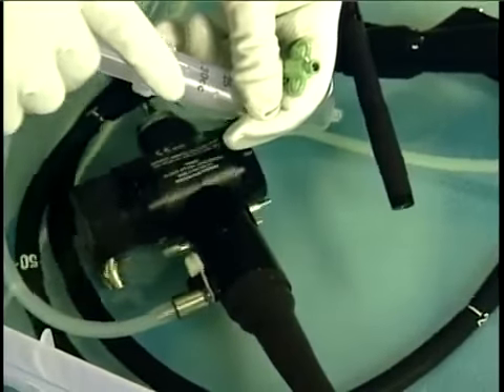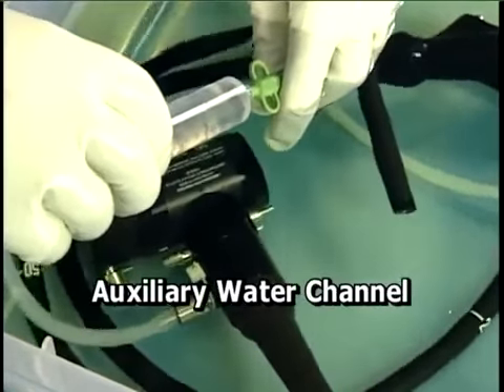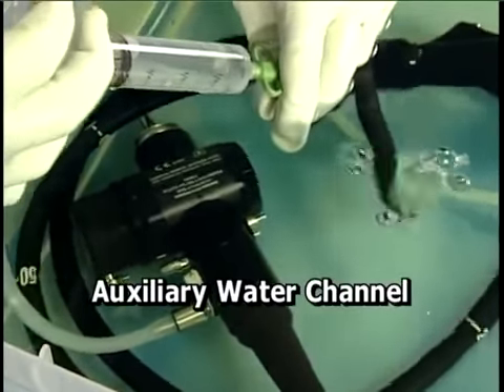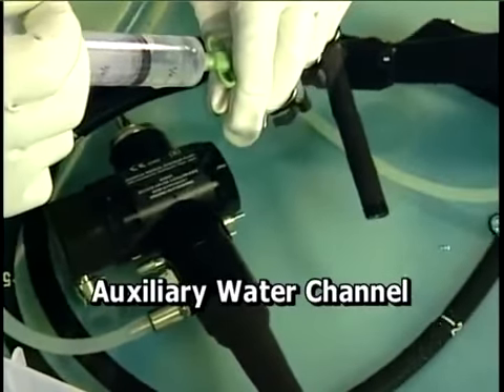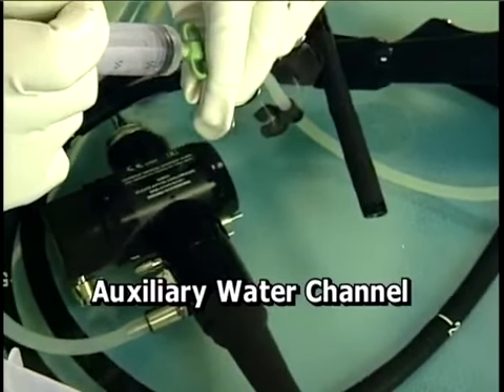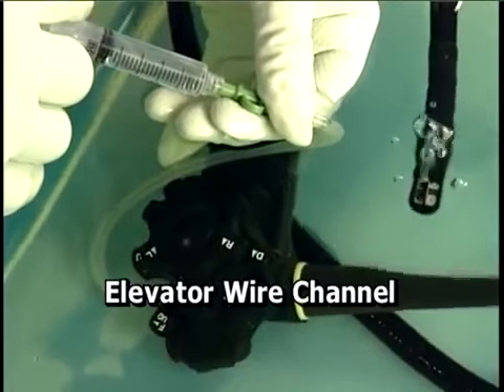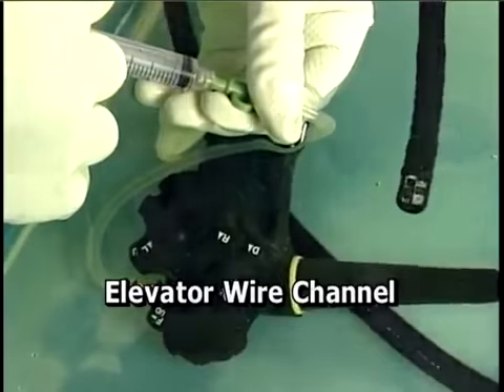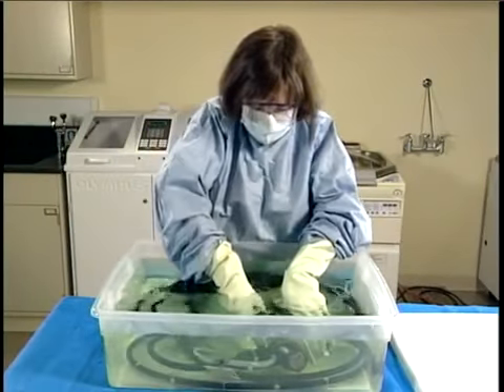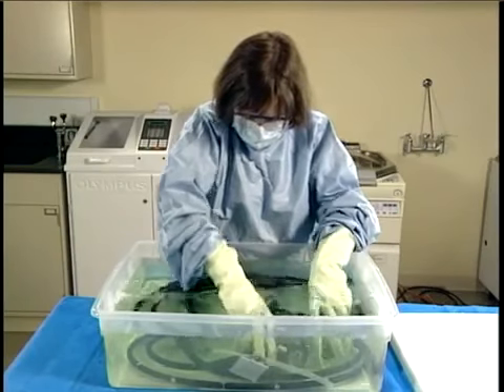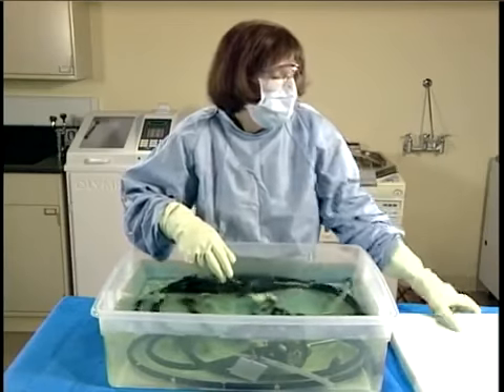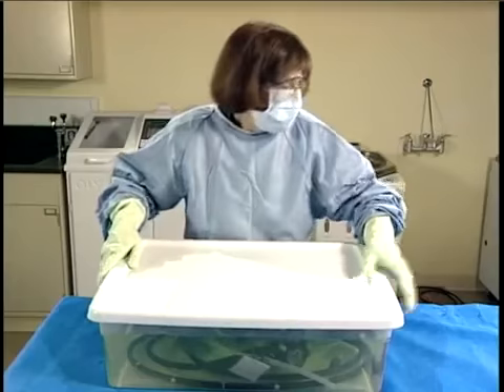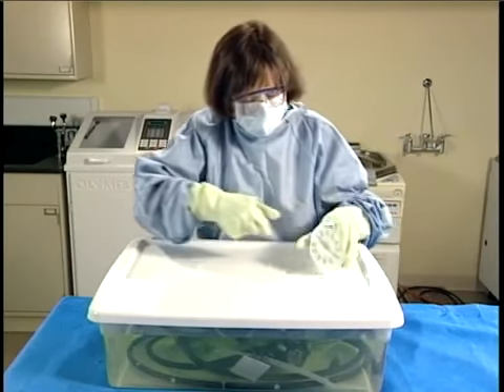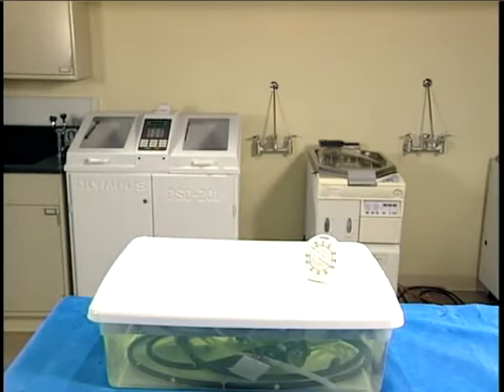If you are reprocessing an endoscope with a special channel, use a syringe to inject disinfectant into the auxiliary water channel. If you are reprocessing a duodenoscope, inject disinfectant into the elevator wire channel. Now, disconnect all accessories while making sure all items remain submerged. Cover the disinfectant basin with a tight-fitting lid in order to contain the disinfectant vapors. Disinfect the endoscope and reprocessing equipment by soaking them in accordance with the disinfectant manufacturer's instructions. Use a timer to confirm you are achieving the proper contact time.